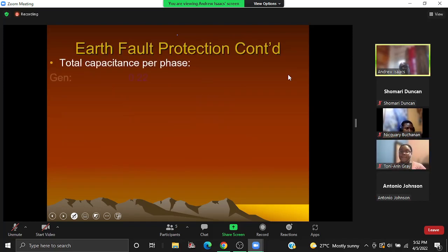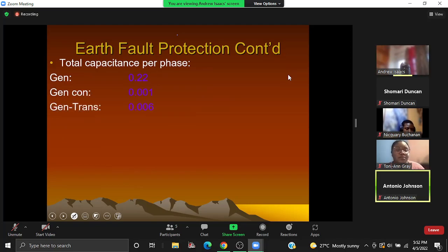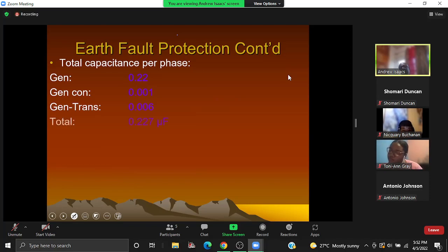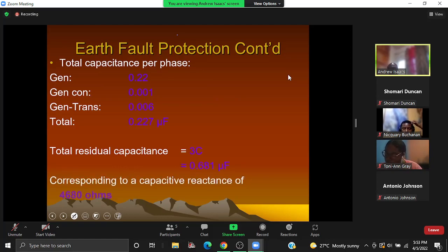Okay, so the total capacitance would be that for the winding, the connections, and the capacitor. We consider them to be in parallel, so we just add them. And from this, we can find the capacitive reactance, so the total capacitive reactance based on these connections at system frequency. My apology, I forgot that part. All the values that we had given were per phase. So for the three phases, we get 0.681. And then we can find the equivalent reactance. And that gives us 4.68 kilo ohms.